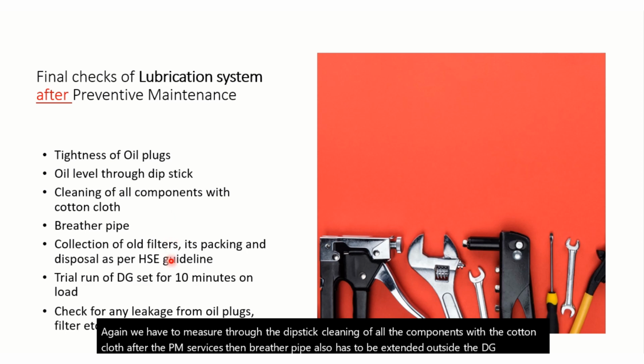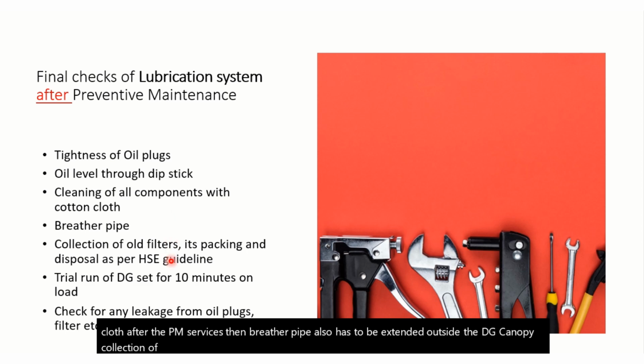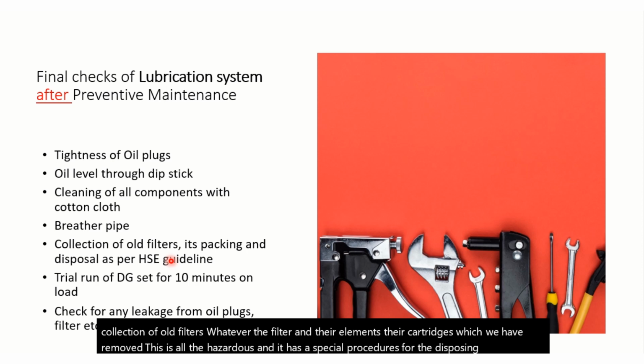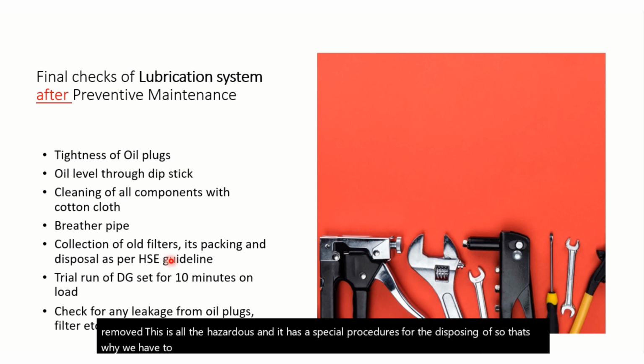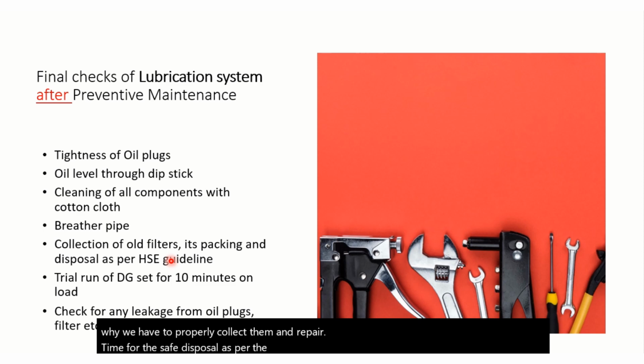Collection of old filters, whatever the filter and their elements, their cartridges which we have removed, this is all hazardous and it has special procedures for disposal. So that's why we have to properly collect them and repack them for safe disposal as per the corporate HSE guidelines.